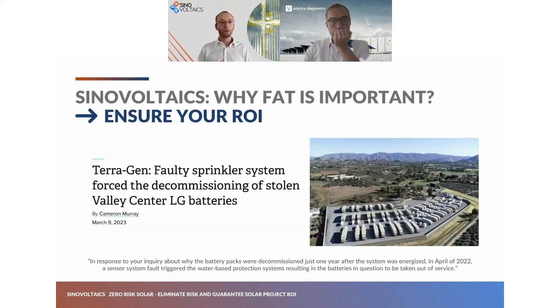Second is to ensure your return on investment. And here, this is a really interesting point. You want to check that the performance of your BSS is as expected, according to your BSS specifications. For this Valley Center project in the US, it's a bit of a funny story, because the return on investment couldn't be met because one or more containers got decommissioned because of a faulty component.